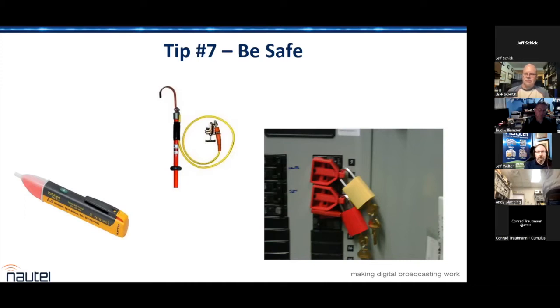I had a guy in Paraguay who shut down a 200 kilowatt AM and very dutifully grounded the output of the transmitter. But it was 700 feet from the transmitter to the base of the tower, with an ATU in the middle. So electrically speaking, who knows what the base impedance of that tower was with the transmitter grounded so far away. I can tell you it wasn't a short circuit to ground, because another 200 kilowatt transmitter two miles away, still on air, put enough signal into his antenna to give him second degree burns when he touched it.